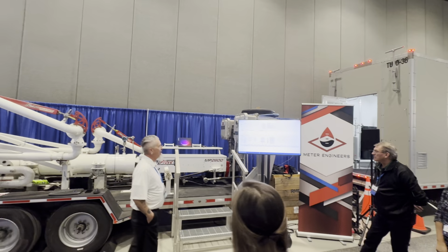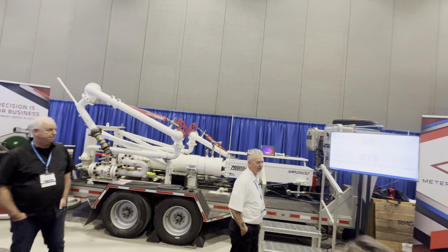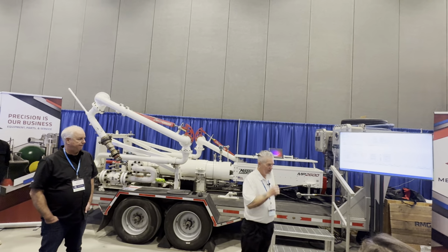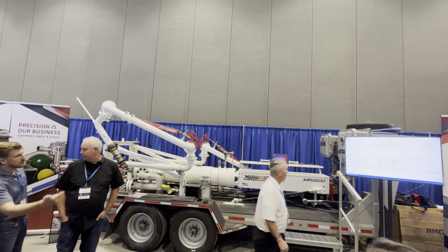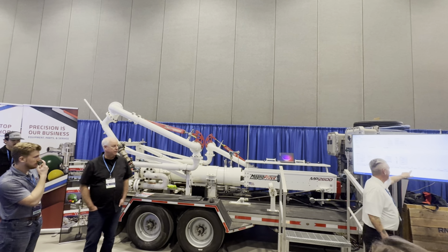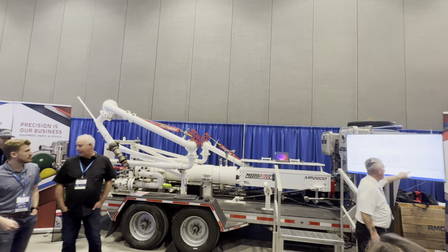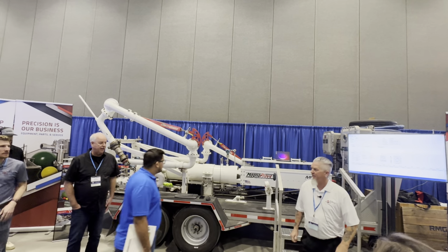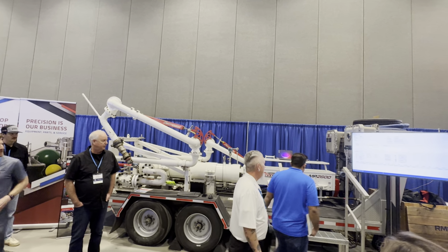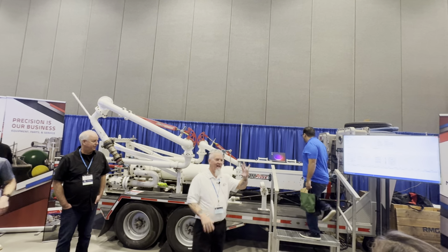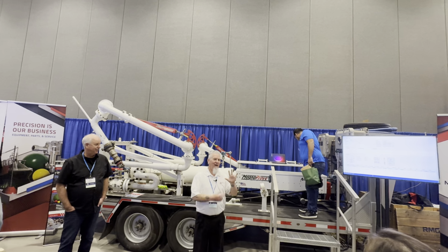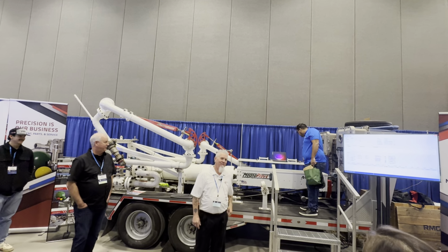So this will continue. I gotta set it for 5 out of 5, and then go up to 20 passes if I need it. So right here now we're running basically a 1.003 on the meter factor. Just keep your fingers out of the cabinet, because I've been without mine longer than you guys, so I might just put it in my pocket and take it with me.